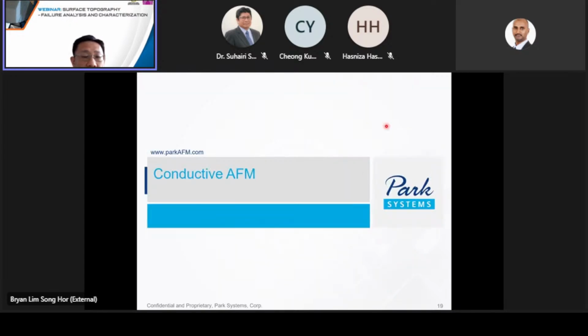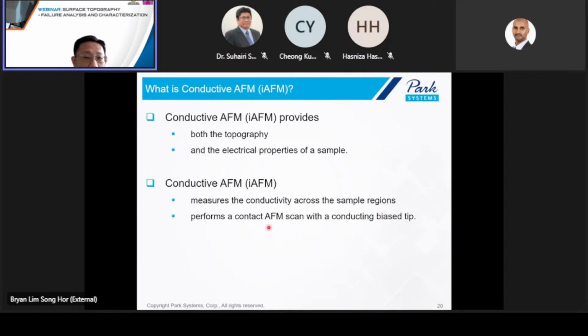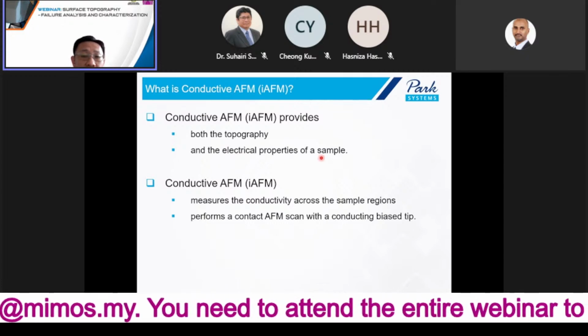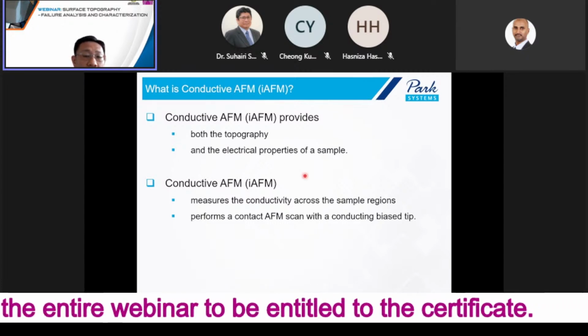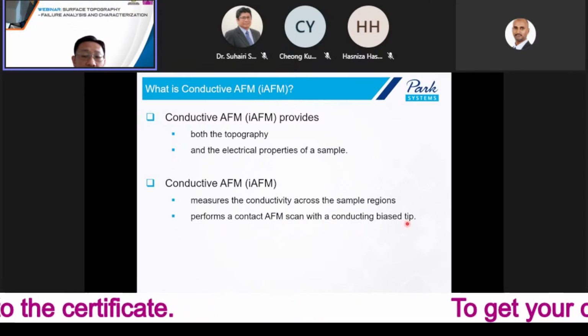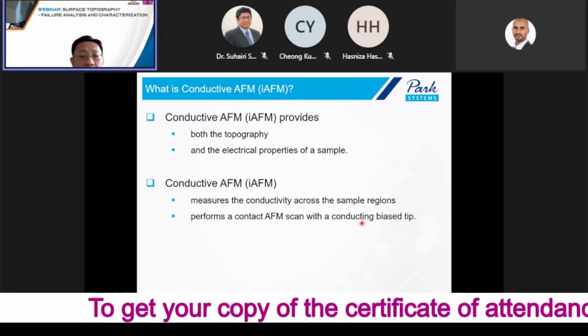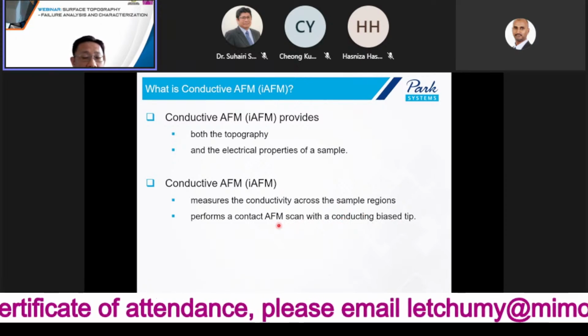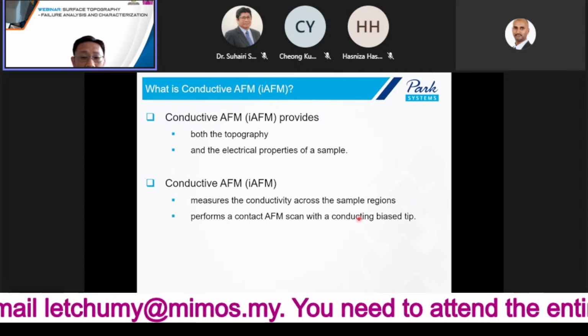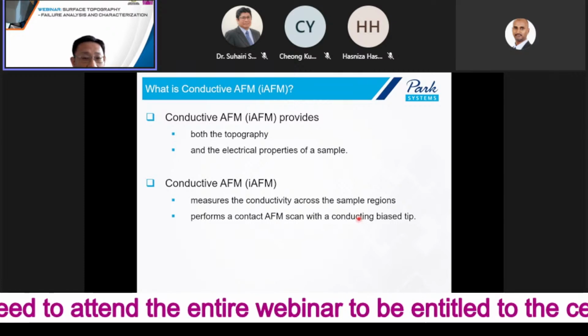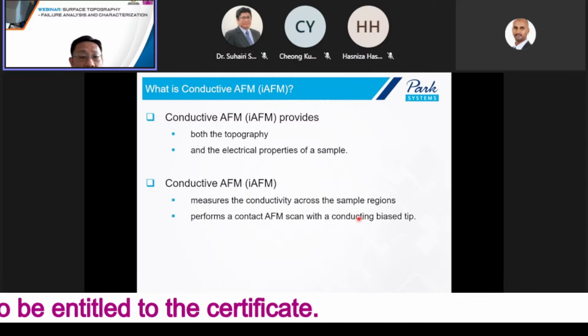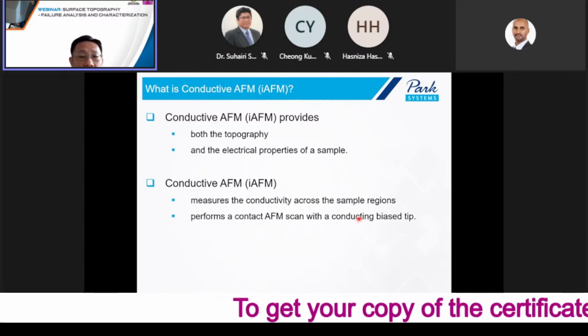So one of the most commonly used modes is conductive AFM. As the word conductive suggests, we are trying to find whether the surface is conductive or not. So conductive AFM measures the topography and also the electrical properties of the sample at the same time. How it does that is by using a tip which has a conductive coating. For this kind of special probe, they put a layer of platinum or gold or even diamond-doped coating on the tip, and they are able to measure the current passing through the surface. And we can apply some voltage on the sample as well.